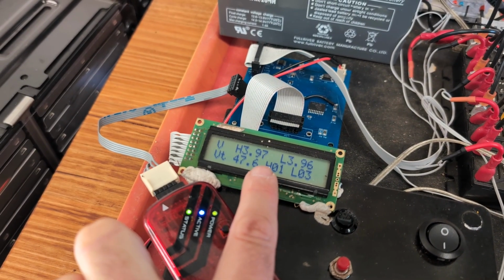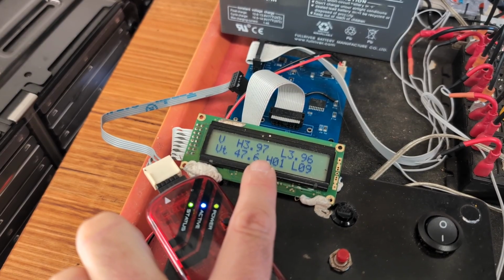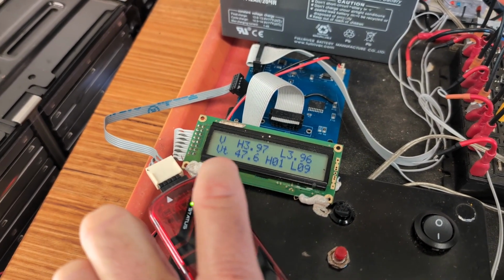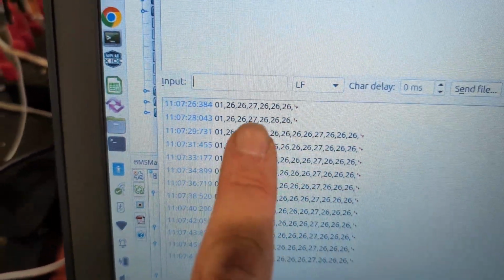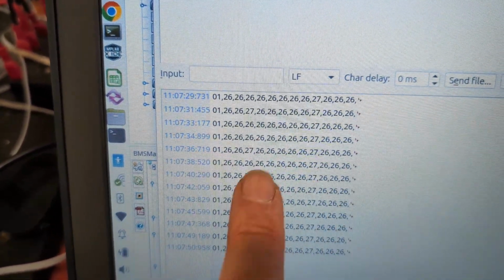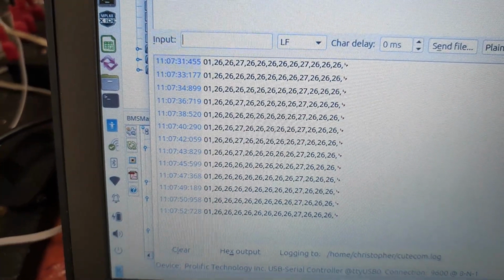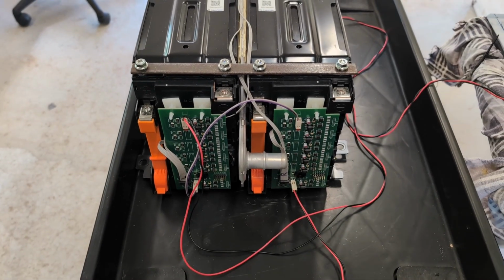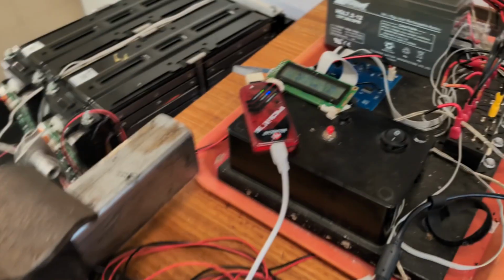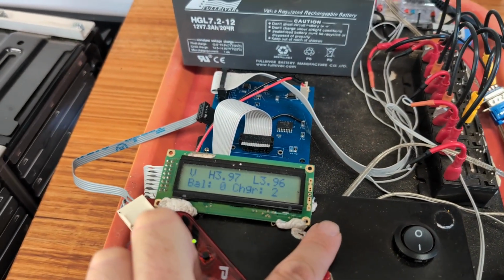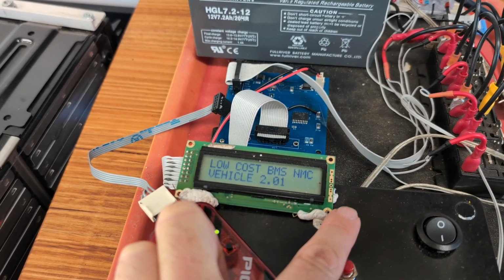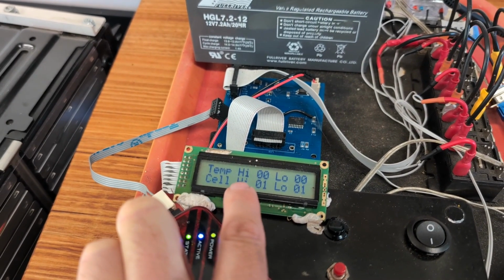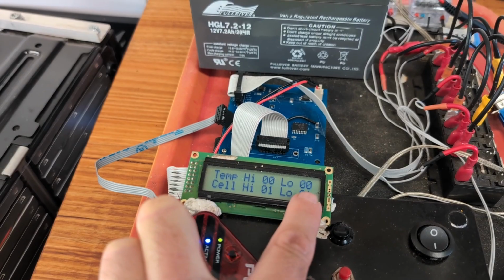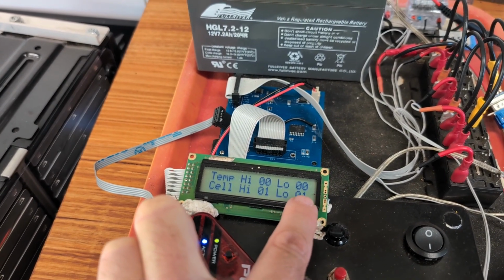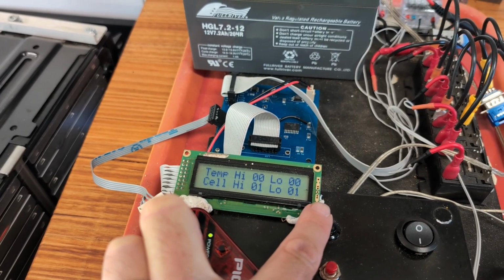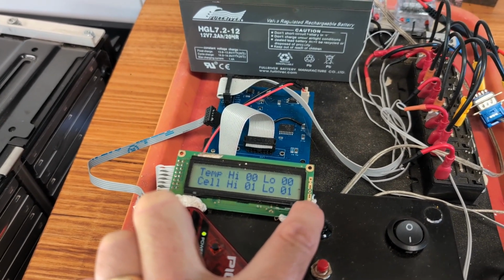And so all of the cells on that other side are 3.97, so 3.96 to 3.97. On the computer here, we've now gone from 6 cell voltages up to 12 cell voltages. Next thing to do is to plug in the temperature sensors. So on our master here, we have a temperature readout, and at the moment the highest is 0 degrees and the lowest is 0 degrees, and that's why we have the fault at the moment. Fault number 9 is low temperature.